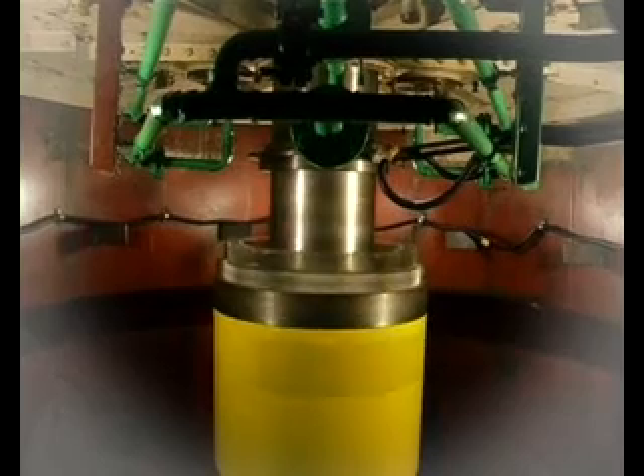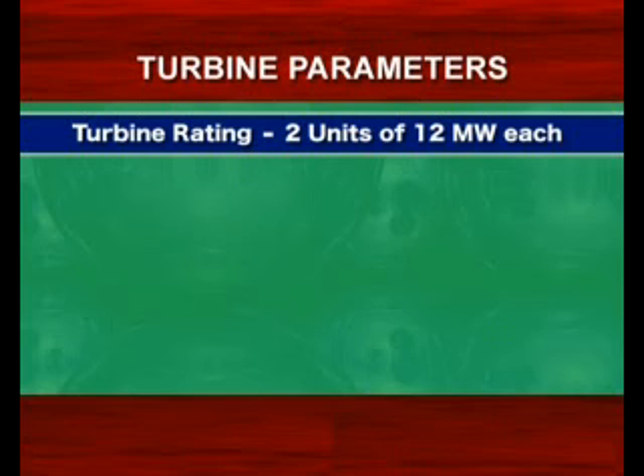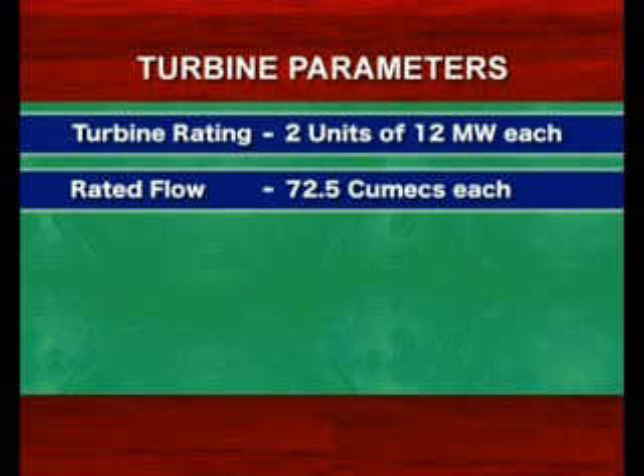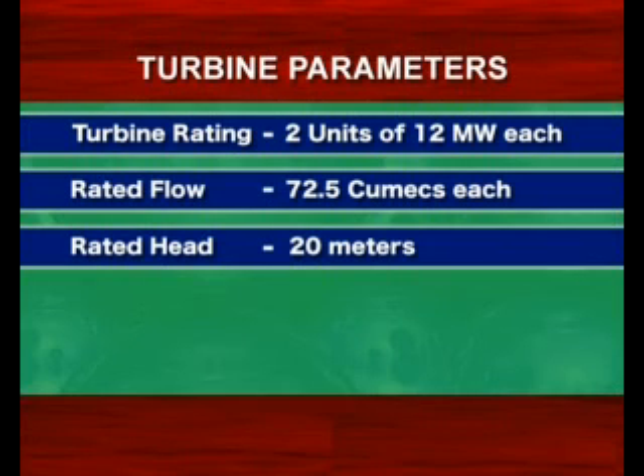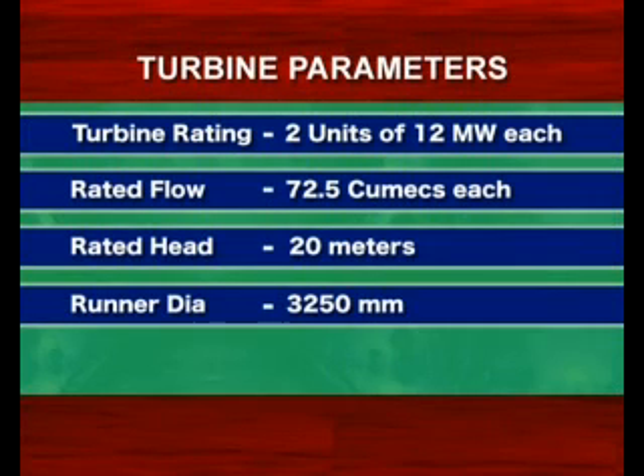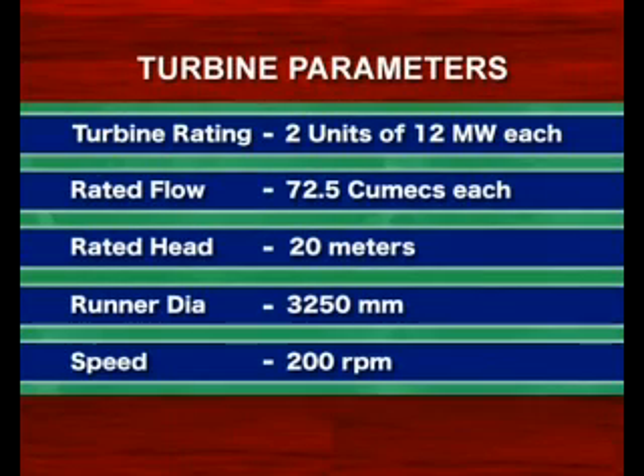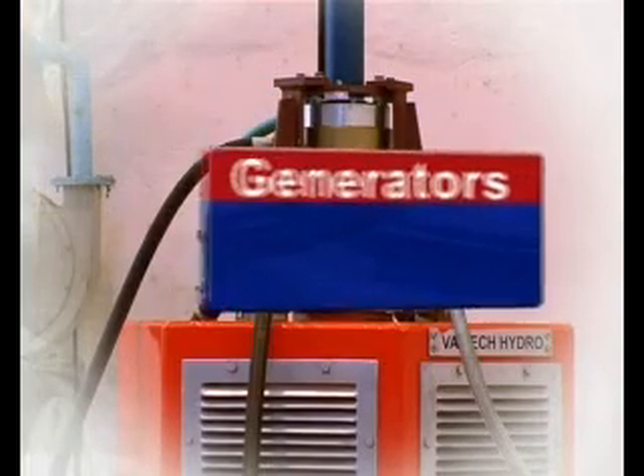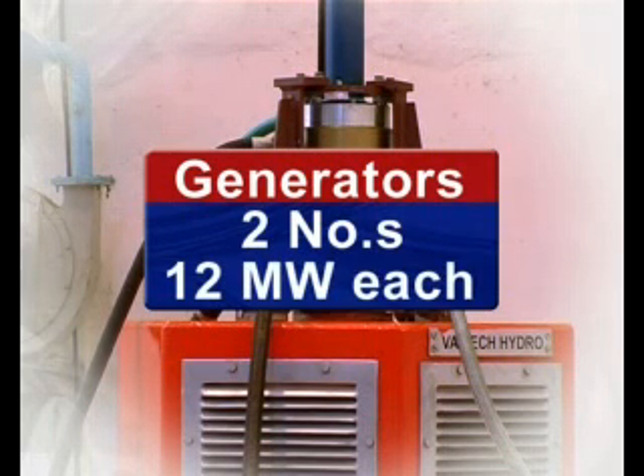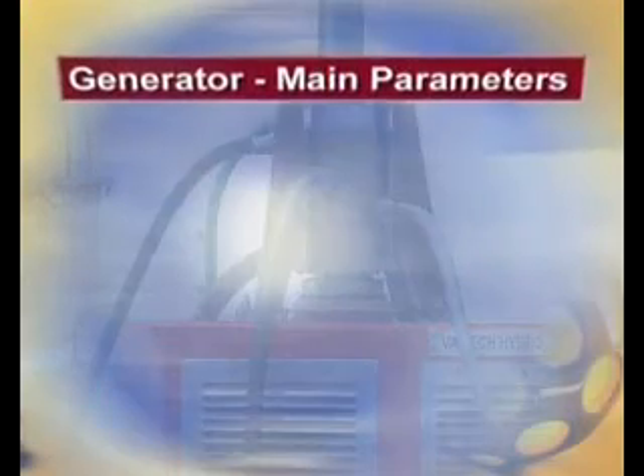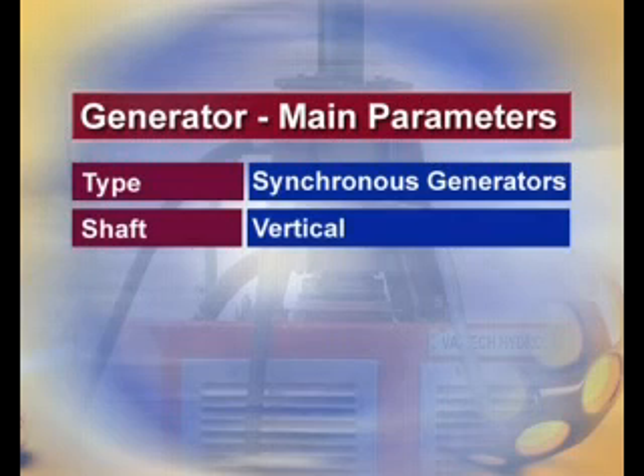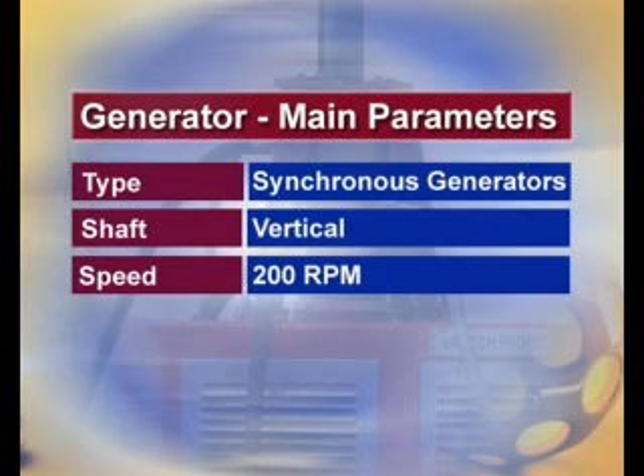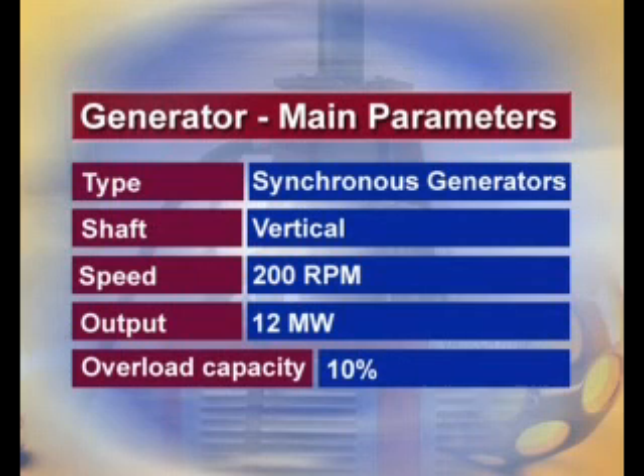The turbines will be vertical full Kaplan with adjustable guide vanes and adjustable runner blades. The main parameters of the turbines are: turbine rating 2 units of 12 megawatts each, rated flow 72.5 Cumecs each, rated head 20 meters, runner dia 3250 millimeters, speed 200 RPM. The scheme will have two numbers of 11 kV synchronous generators of 12 megawatts each, coupled with vertical full Kaplan turbines. The main parameters of the generators are: type, synchronous generators; shaft, vertical; speed 200 RPM; output 12 megawatts; overload capacity 10%.